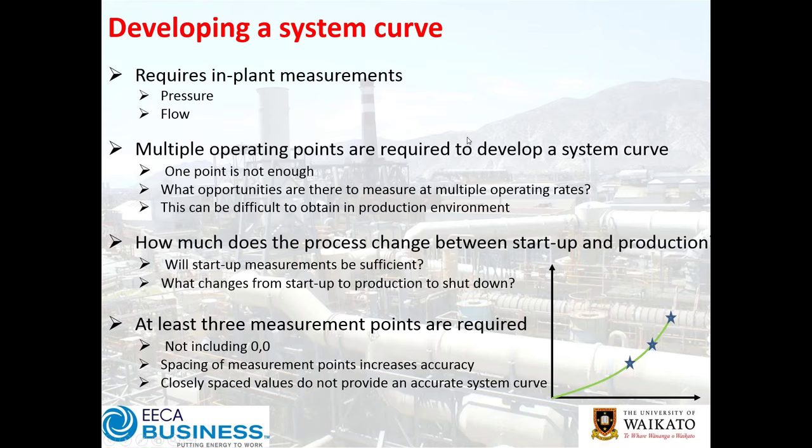To develop a system curve we need to actually measure pressure and flow — theoretically looking at it is not going to cut the mustard. Multiple operating points are required; one point is not enough. One point just tells you the fan can do a certain pressure at a certain flow — it has no indication of how steep the curve is. We try to have at least three points, and obviously the more points we have the better.